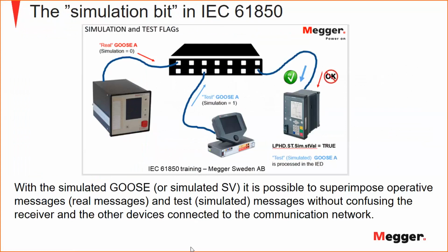So, as I said, here we have 2 relays, and here we have a test set, and one relay is sending a real GOOSE A to relay B, which is subscribing, that is receiving the GOOSE message. And we have the Megger test set, the Omicron test set, the Doble test set, any test set. This is a standard word. Everybody has to behave in the same way. And the Megger test set sends a GOOSE message with the simulation bit 1. Both messages are on the network, both, but the relay doesn't consider the Megger GOOSE message until we tell the relay to receive simulated messages. Very, very simple, but it has to be understood.